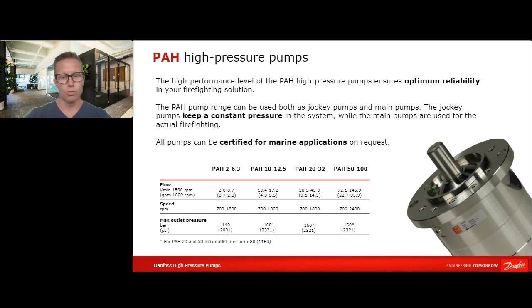Also, there's no oil inside the pump. It means that the pump is being lubricated by the media itself. This also makes service and maintenance very easy. And you don't have to, of course, make any oil change. They come in various sizes, as you can see here in the table below, fitting to the different needs of the applications here. The larger pumps we have are the ones that are mainly used as a main pump in a firefighting skid.